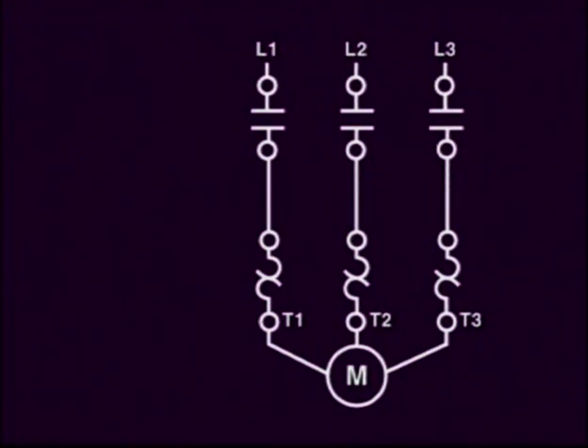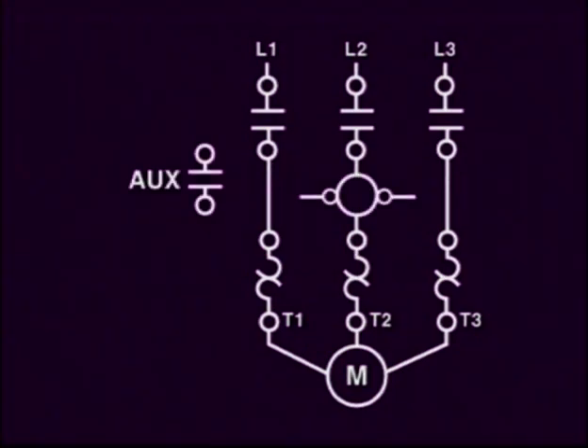The coil of the starter, which energizes the power contacts and the auxiliary contacts, is represented in this configuration like this, while the normally closed overload contacts are graphically placed like this, in close proximity to the overload coils. In fact, this graphic representation follows very closely the actual location of the components that form the motor starter. At the top, we have the line power terminals. Below, the coil and the auxiliary contacts between these two points. The power contacts are sort of behind, while the overload relays and the normally closed overload contacts are right below.